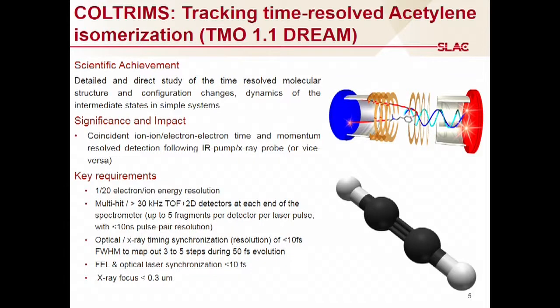And in this case, we have the electrons being detected over here and the ions being detected over here. The reason why you see this thing going loopity-loop is that electrons move a lot faster than ions, so we need to slow them down so they can hit at the same time. So you know that they're in coincidence in a gate window, so you can see exactly what's going on here.